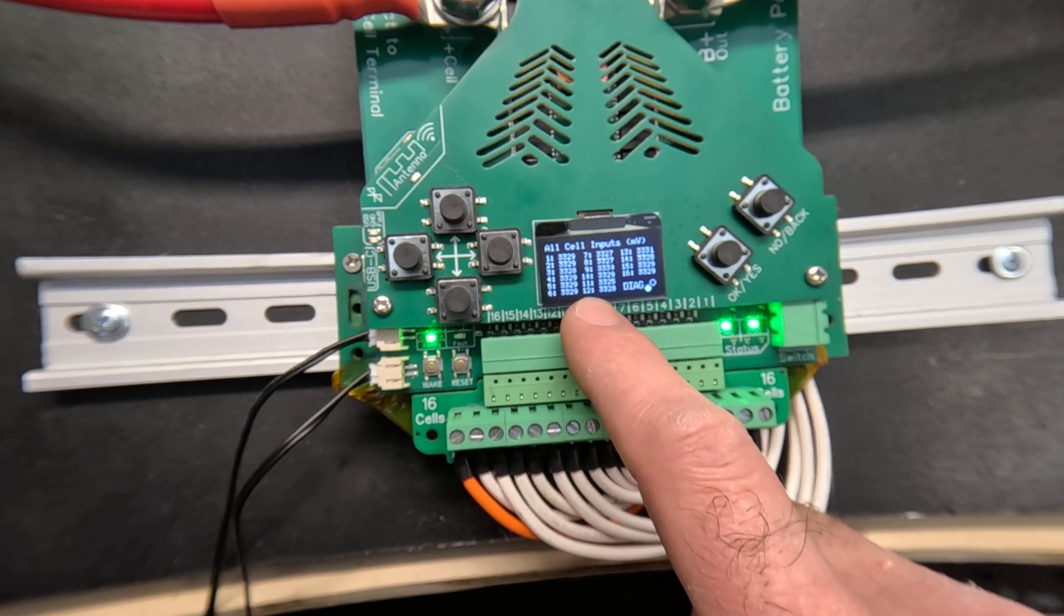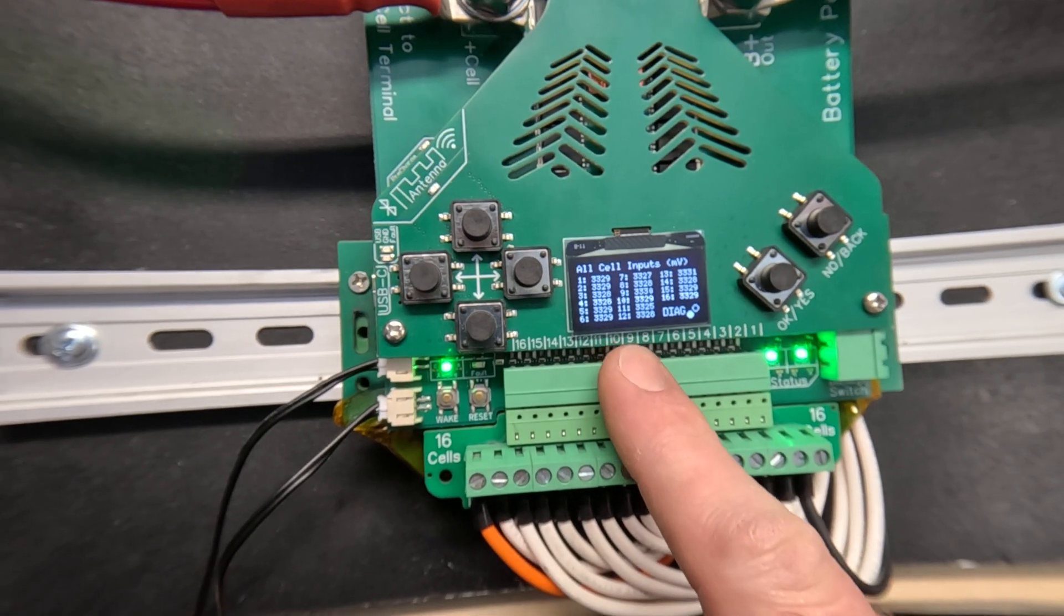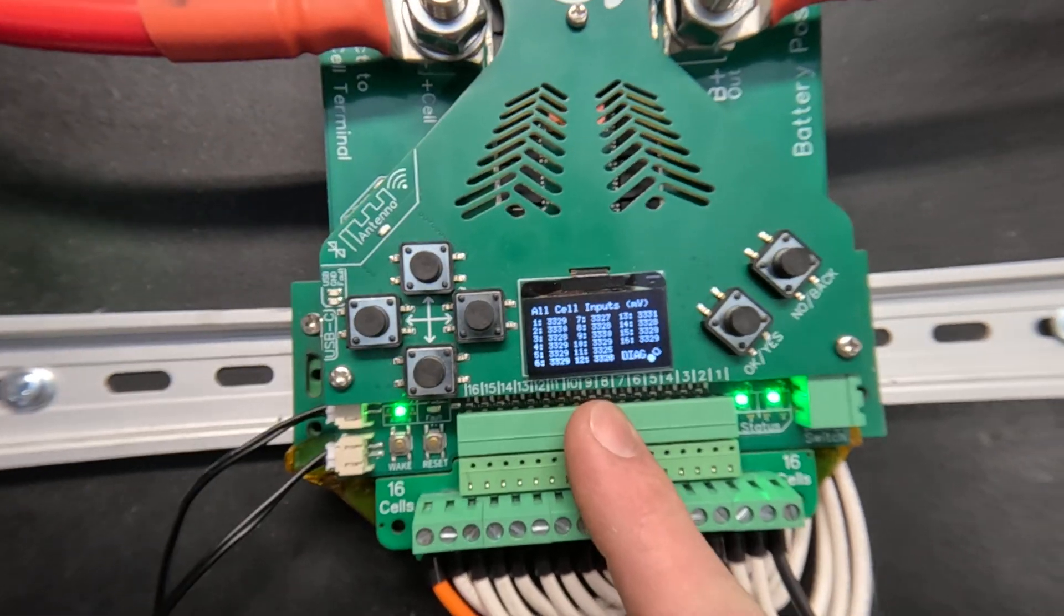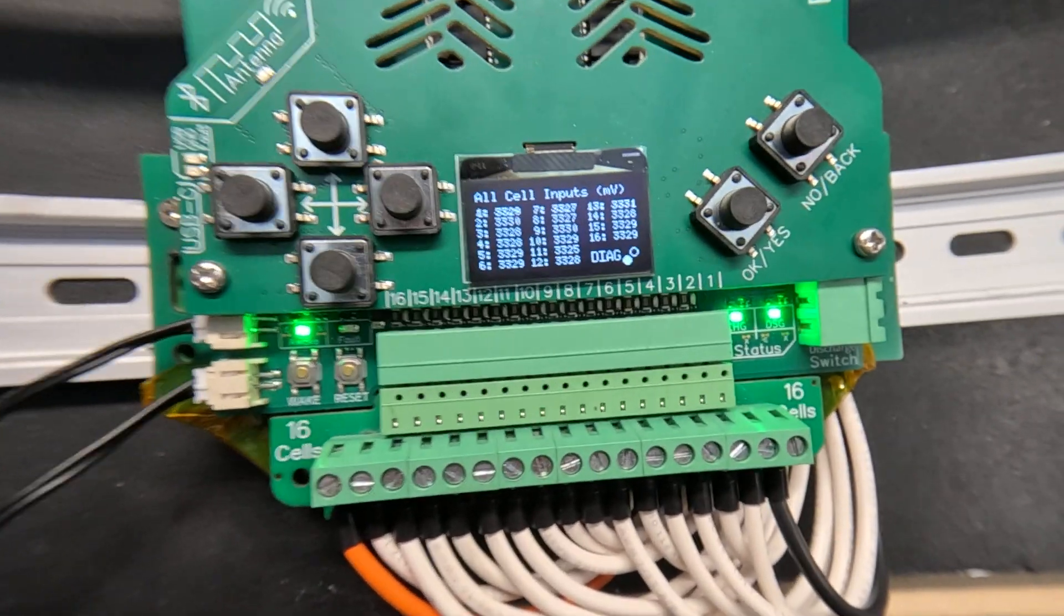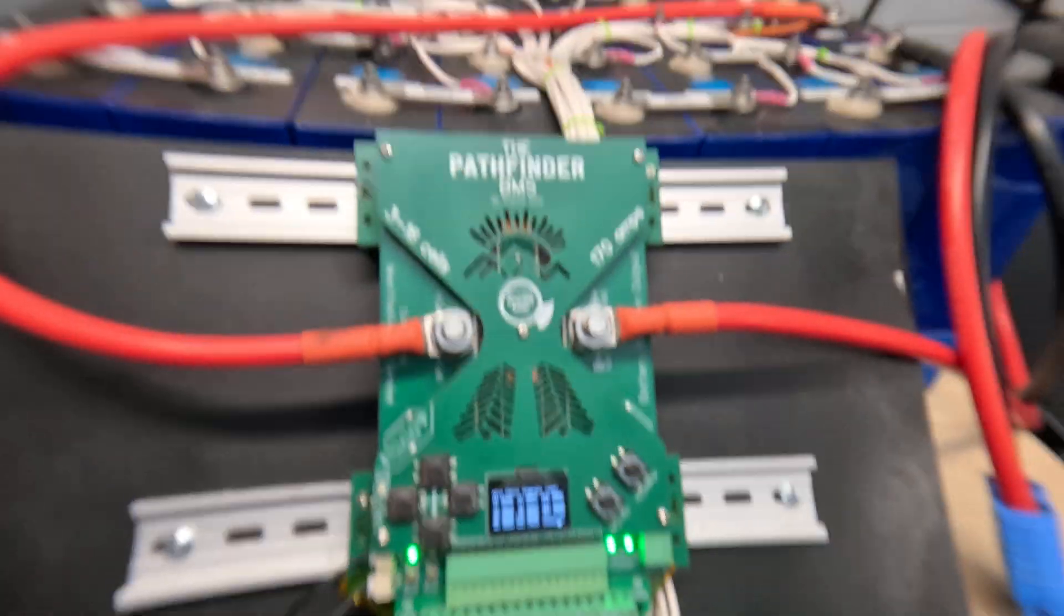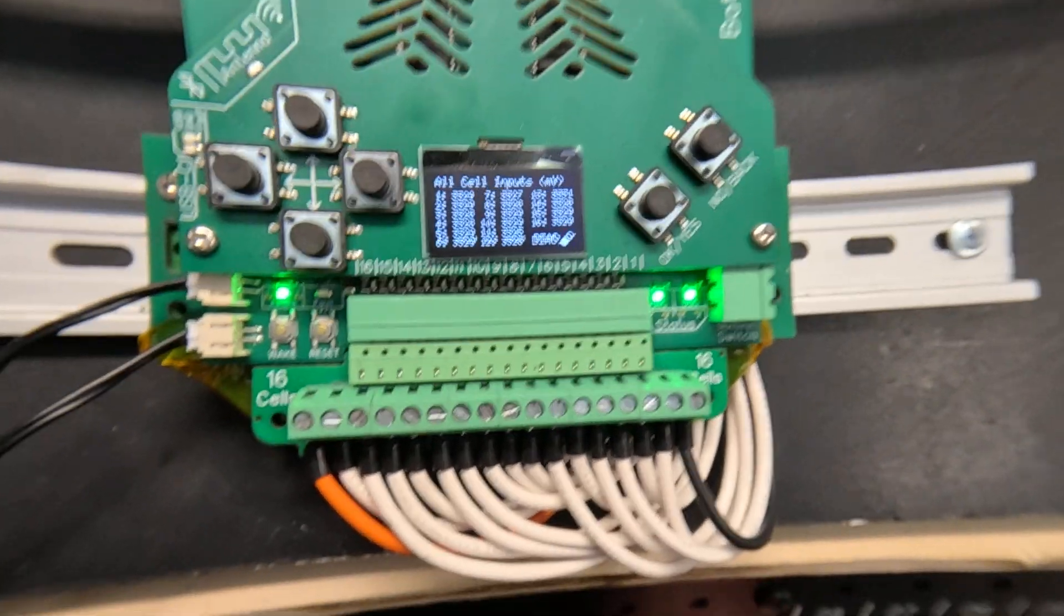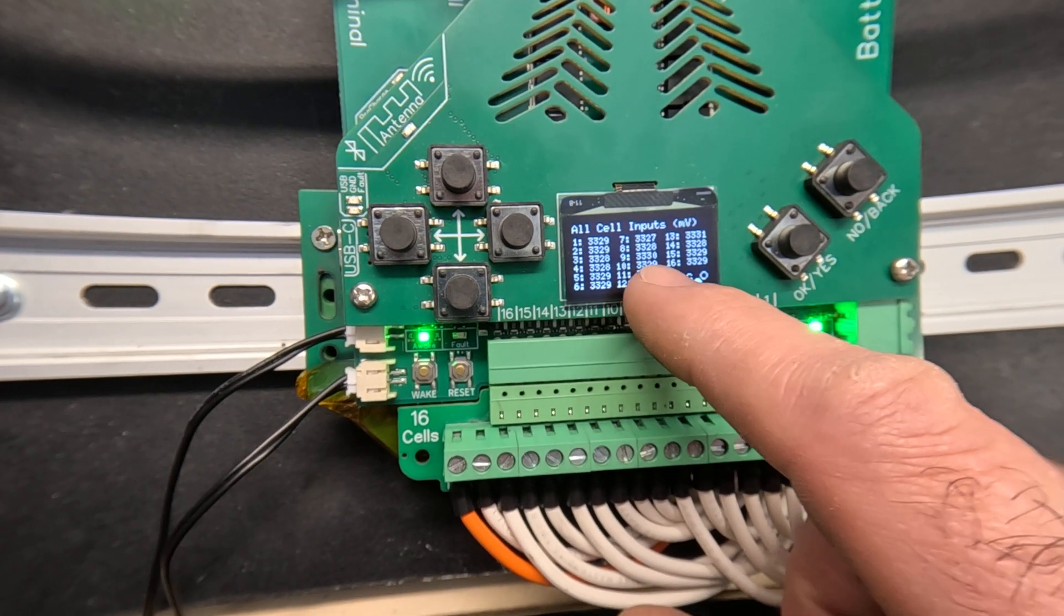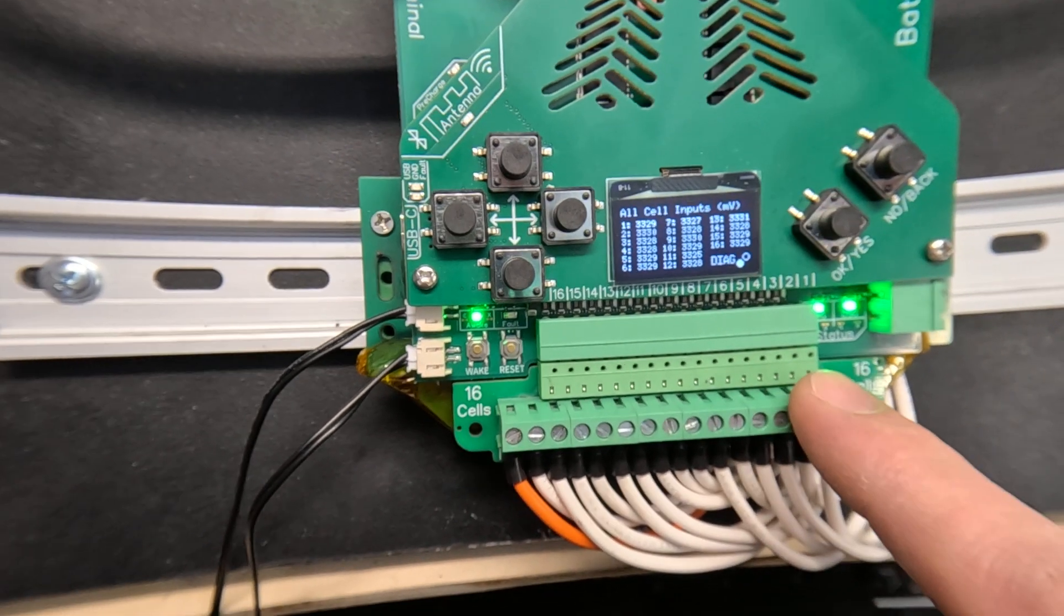The next screen is a diagnostic tool. It shows you all of the cell inputs even if some of them aren't connected. That's going to be especially useful if you have wiring faults or loose wires or corrosion on some of the battery terminals or the bus bars, then you would be able to, it'll actually highlight cells that have a fault.